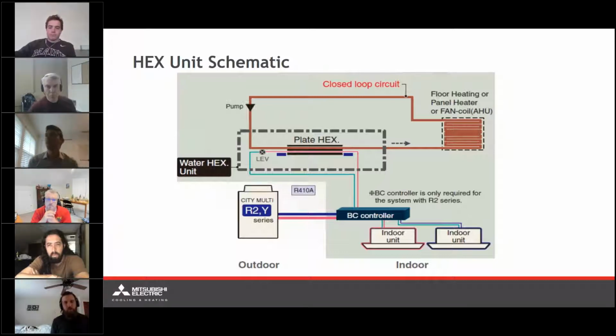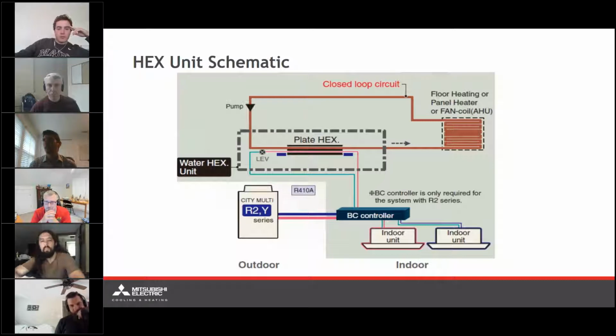So the HEX unit in this instance, as we're working our way downstream from the port of the BC controller, the refrigerant that's going in is going to go through the linear expansion valve, or the LEV, within the HEX unit. The same LEV that's going to be in every single indoor unit, like cassette unit, wall mount. Quite simply, in that heat exchange process, we're going to go through a plate heat exchanger within the HEX unit in order to transfer the heat, refrigerant to water, or vice versa, or removing the heat from the water if we're in cooling mode. In this particular schematic, we have a closed loop circuit, secondary loop, and this is just demonstrating that we could go through a floor heating system, panel heater, or a fan coil itself, an actual air handler with its own hydronic coil built in.